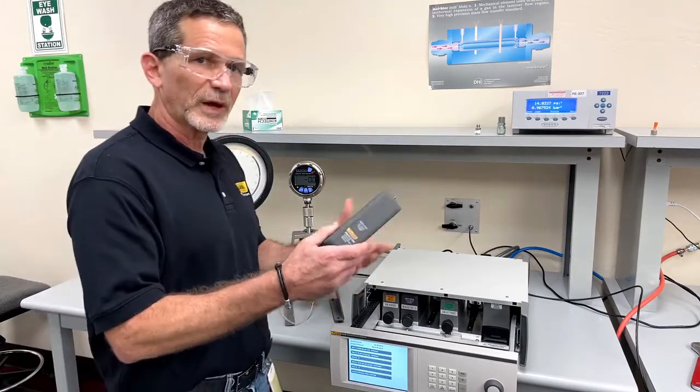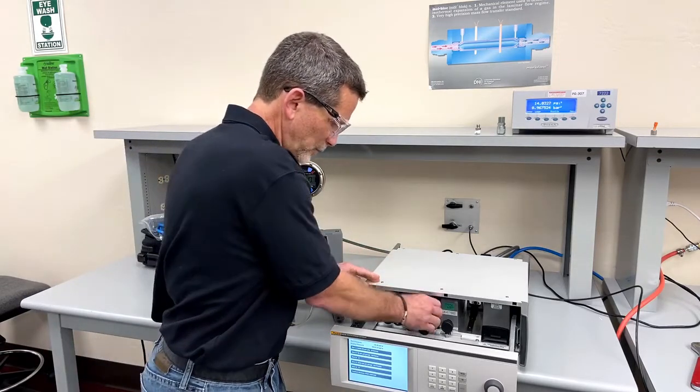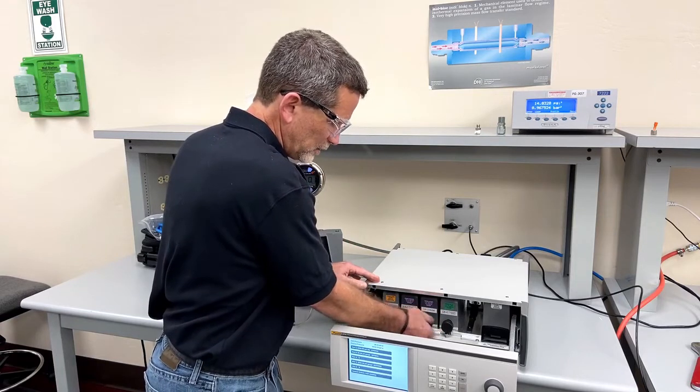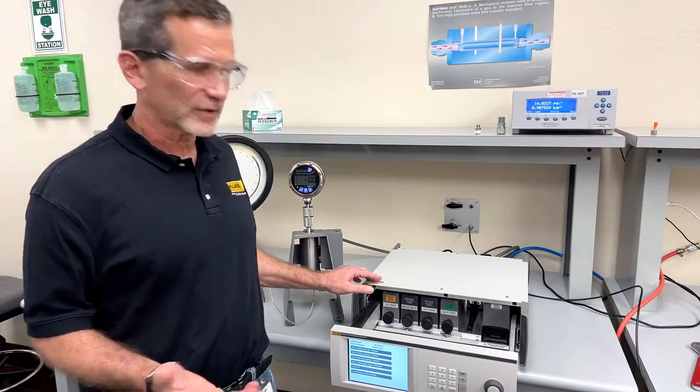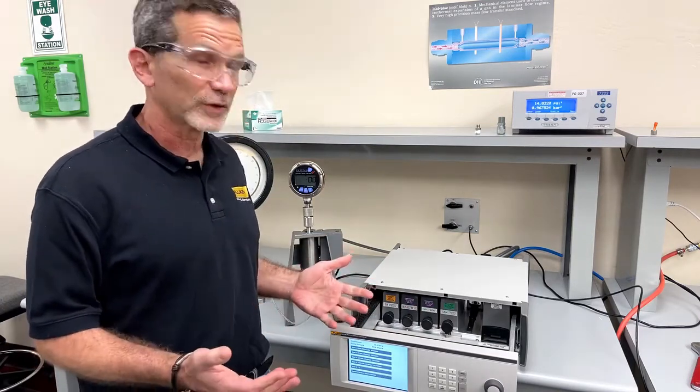When it comes back from calibration, simply reinstall it in the same or a different slot of your choice and wait until you hear the click. That means it's locked in, no torque wrench necessary, and no over-tightening.